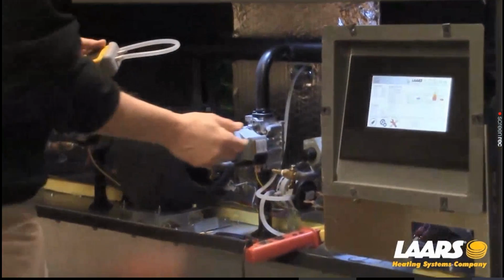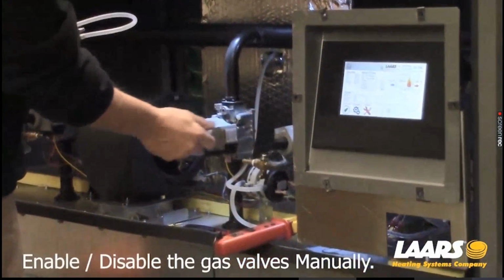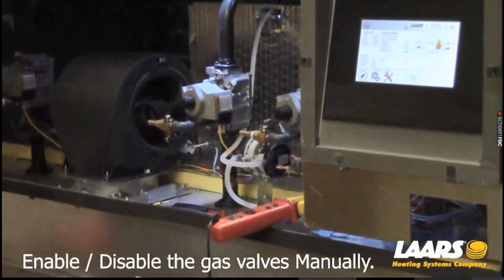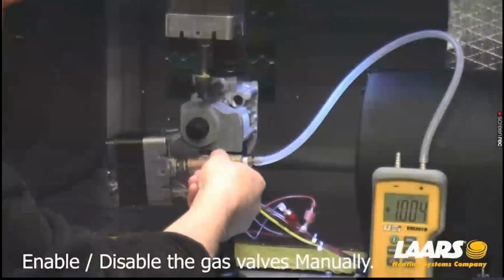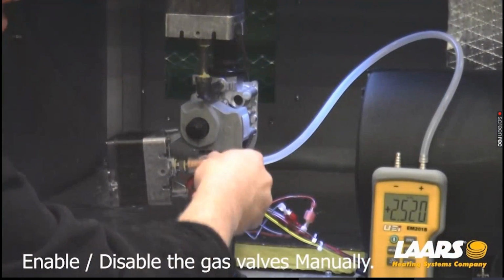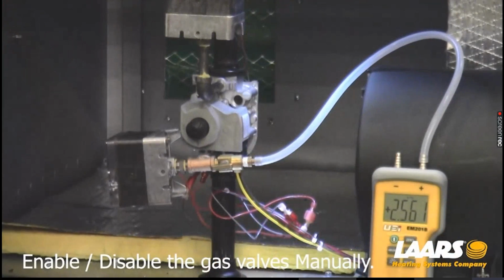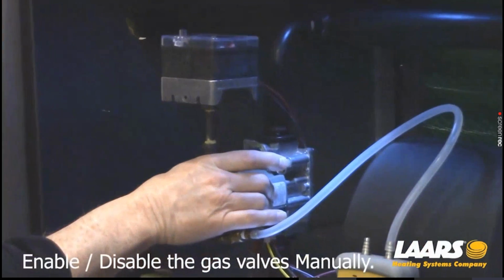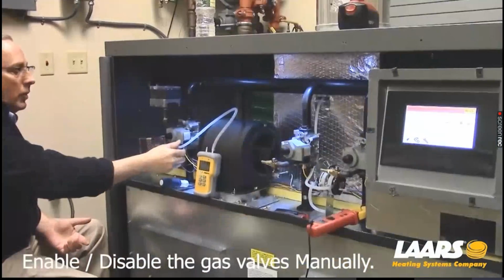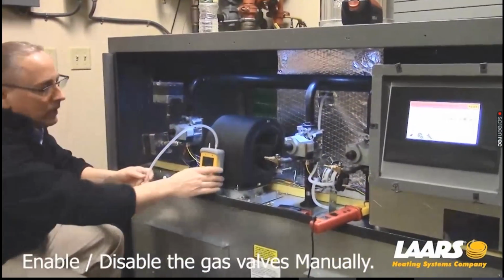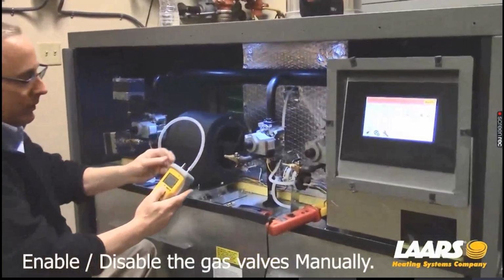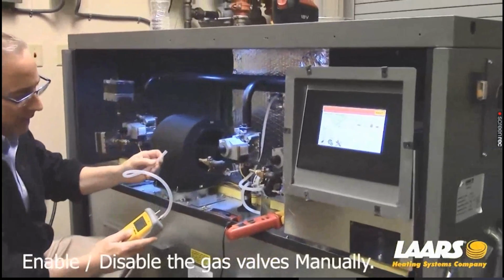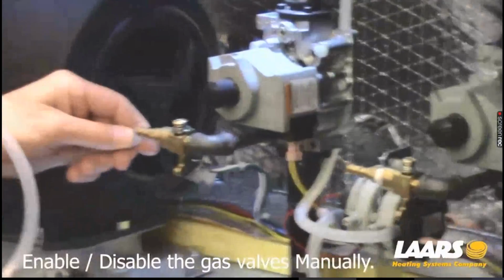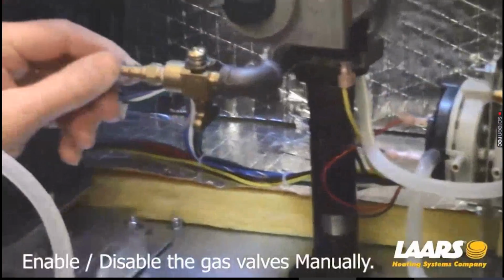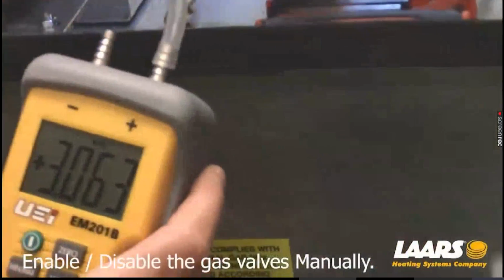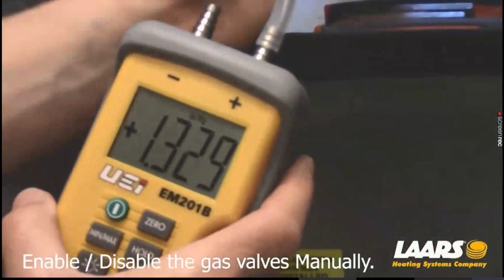With the second option, we'll go in and manually shut off valves 2 and 3. I'll open the butterfly, and I'm looking for 2.5 inches of water column. So now valve 1 is checked and set. Remove my hose, come over to valve 2. Zero out my manometer again. And open my butterfly.